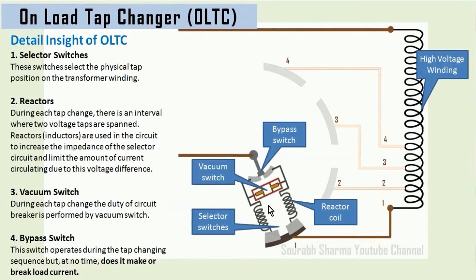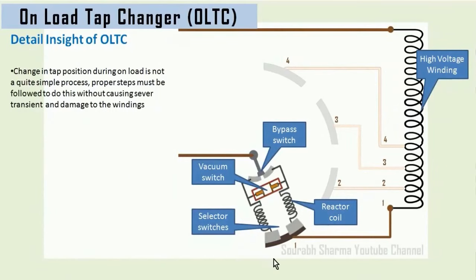The arm which rotates inside the OLTC is made of two parts. The front part is the selector arm, and the back part is known as the bypass switch. The selector arm is made in two parts — the left part and the right part. Both parts consist of a reactor coil, which is simply an inductor that opposes the sudden change in current. Both the left and right parts are connected through a vacuum switch. When the tap position needs to be changed, it must follow a proper sequence; otherwise it may cause heavy sparking and the transformer winding and terminals could get burnt.